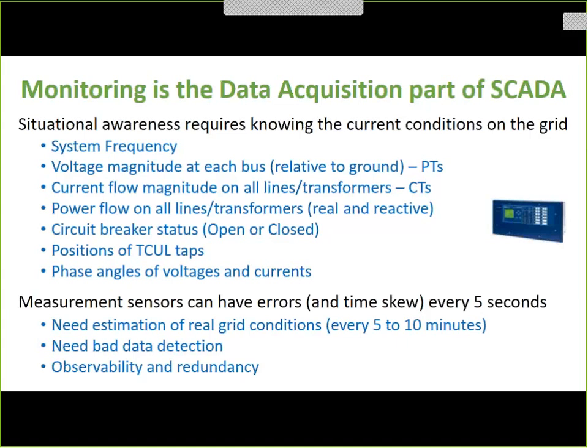Circuit breaker status is a big deal. Is a line open or closed? You may think that's simple, but if you're an operator in a control room, you don't know what's what. And that was a big problem in the New York blackout of 77, I think it was. And they thought a line was out because it registered as 0 megawatt flow. But it wasn't 0 megawatt flow because the line was out. It was just 0 because there wasn't any flow. And that caused confusion. So we monitor the status of breakers.